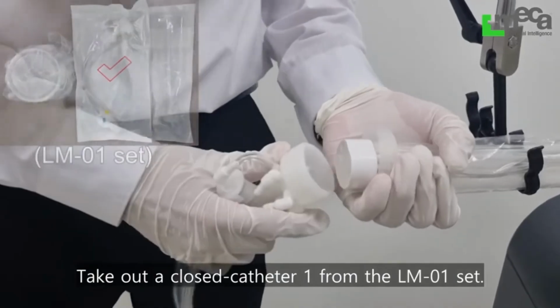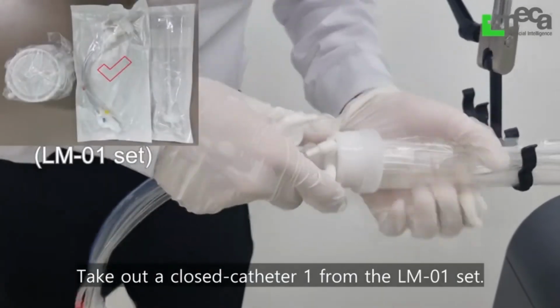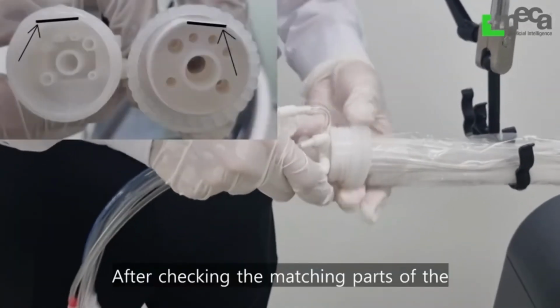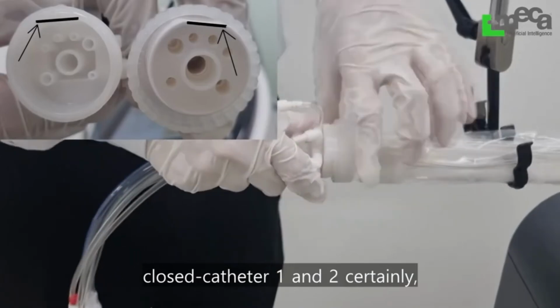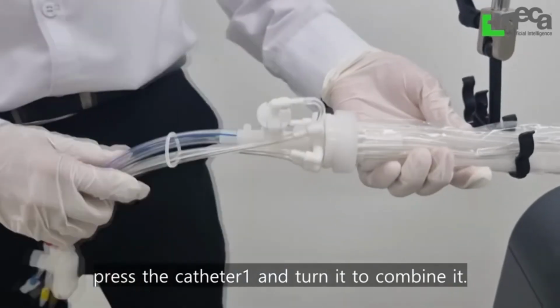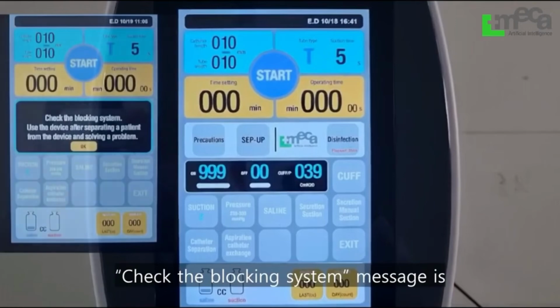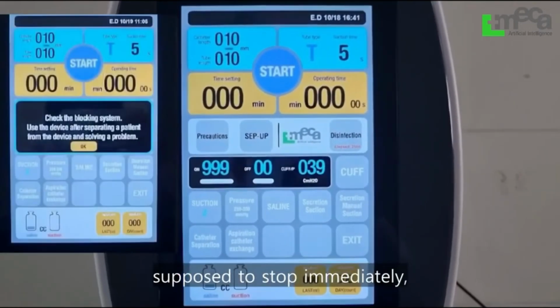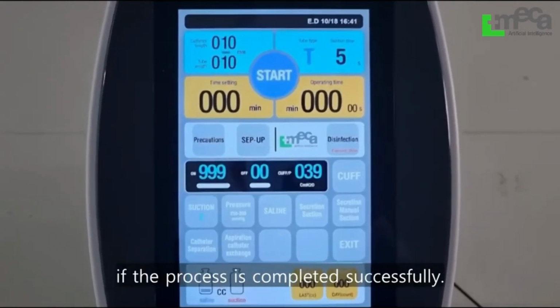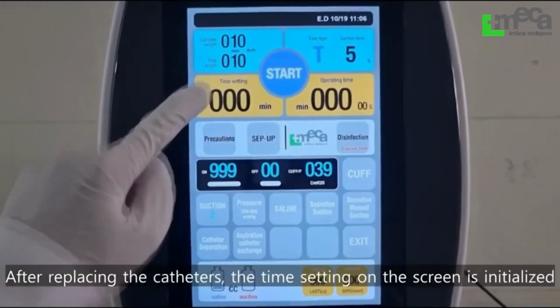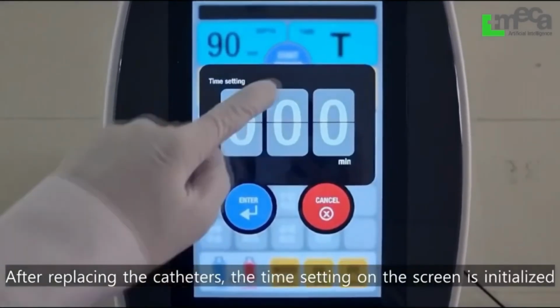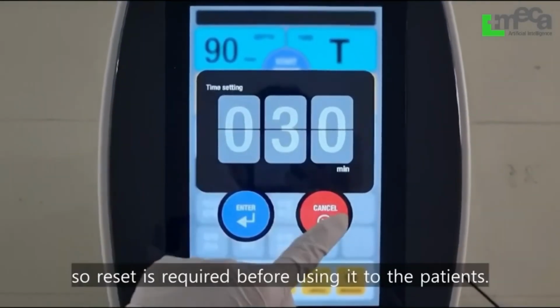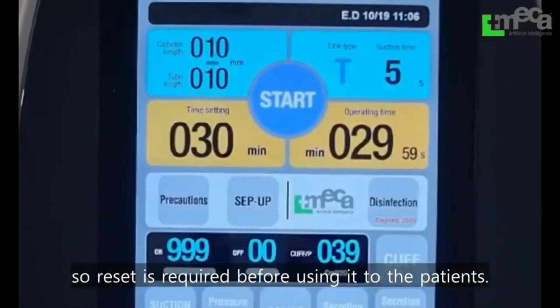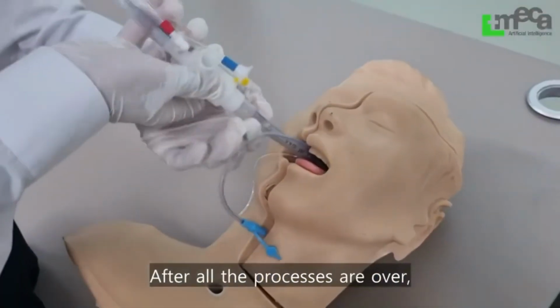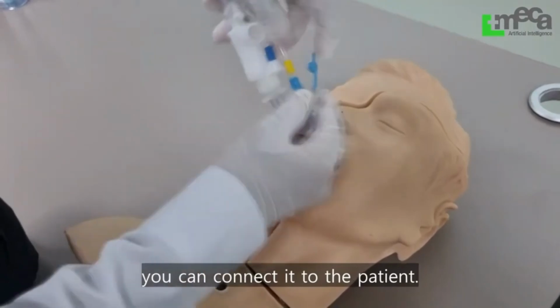Take out a closed catheter 1 from the LM-01 set. After checking the matching parts of the closed catheter 1, make sure to press the catheter 1 and turn it to combine it. Check the blocking system message is supposed to stop immediately if the process is completed successfully. After replacing the catheters, the time setting on the screen is initialized, so reset is required before using it on the patients. After all the processes are over, you can connect it to the patient.